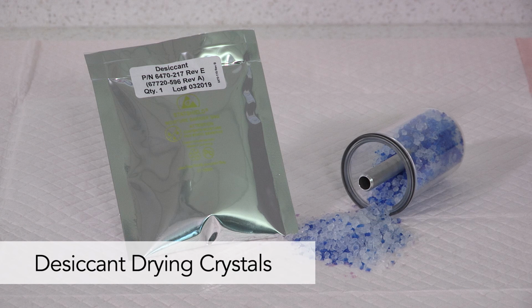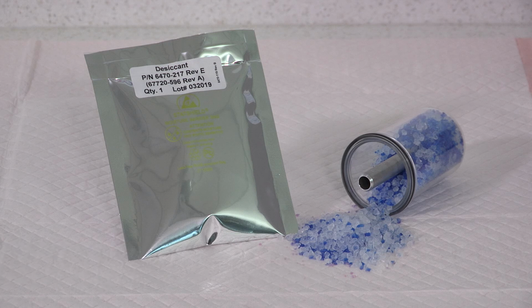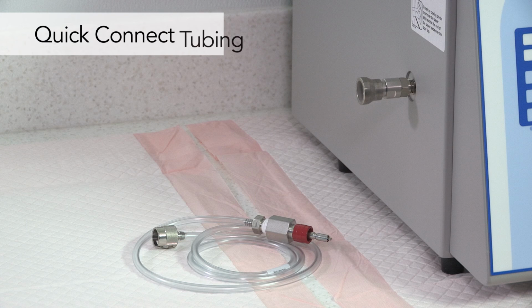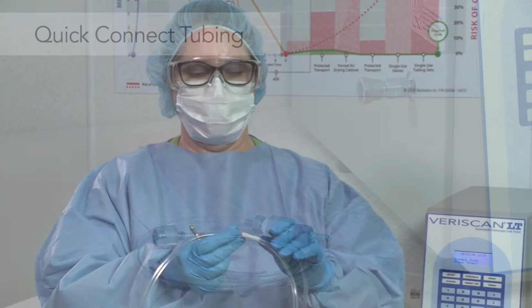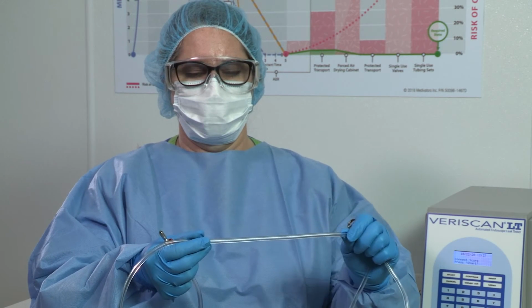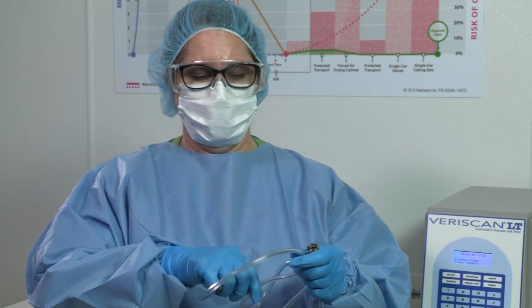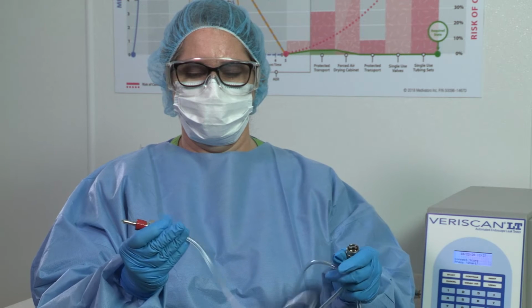The desiccant drying crystals must be installed before leak testing an endoscope, as they ensure that only dry air is used during leak testing. See the desiccant drying crystals segment for instructions. A quick connect tubing is used to connect the VERISCAN Leak Tester to your flexible endoscopes. Before attaching, inspect the quick connect tubing and replace if there is damage or any indication of wear.